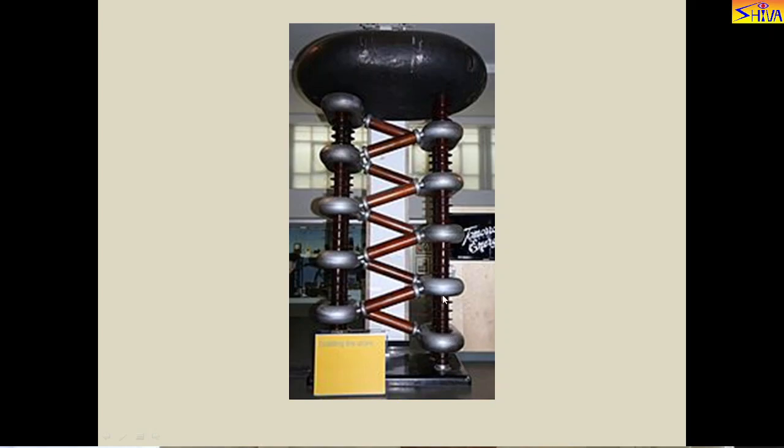These are the capacitors 1, 2, 3, 4, that is smoothing capacitors. These are 1, 2, 3, 4, that is oscillating column capacitors. And this structure, that is dome type structure or corona ring, is provided to avoid corona at the high voltage. So this is a 4-stage circuit.